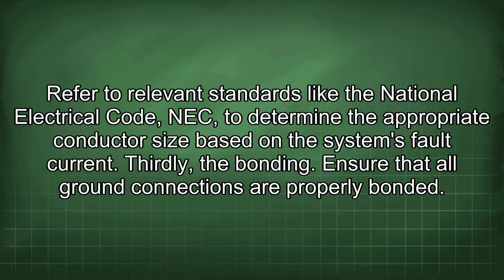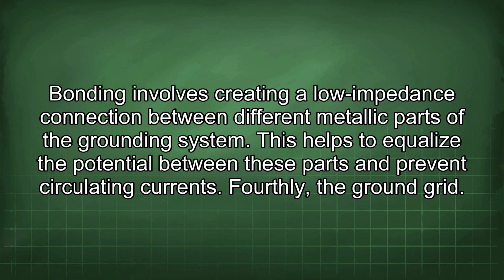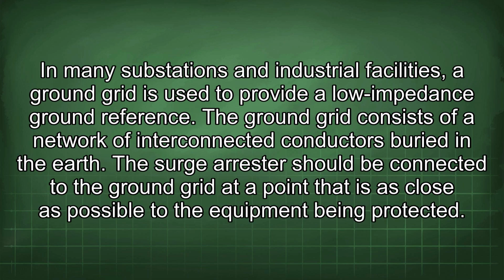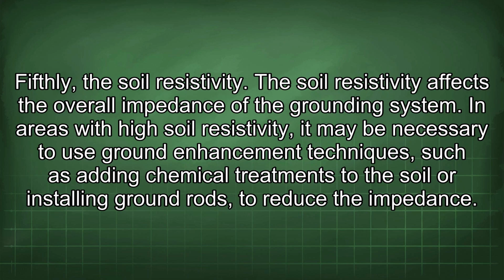Ensure that all ground connections are properly bonded. Bonding involves creating a low impedance connection between different metallic parts of the grounding system. This helps to equalize the potential between these parts and prevent circulating currents. Fourthly, the ground grid. In many substations and industrial facilities, a ground grid is used to provide a low impedance ground reference. The ground grid consists of a network of interconnected conductors buried in the earth. The surge arrestor should be connected to the ground grid at a point that is as close as possible to the equipment being protected. Fifthly, the soil resistivity.